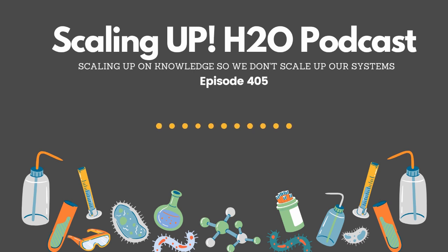Automating the blowdown helped us maintain water quality and reduce the risk of scaling and corrosion at any time. Normally, when it comes to saving costs, the customer says we always need to increase our concentration ratio. I'm sure it was no different here, but now you have all these solids coming in with the effluent treated water, because I'm sure they asked for it.